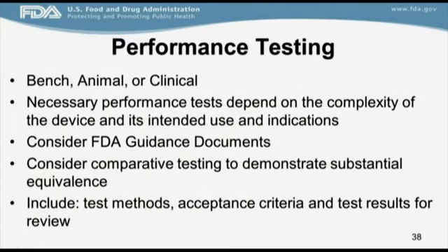Next, we're going to talk about performance testing. Performance testing can be bench, animal, or clinical. Performance testing is actually determined specifically to the complexity of your device and its intended use. So every 510K is going to have different performance testing, depending upon the difference in the technological characteristics or the differences in the new device compared to the predicate.